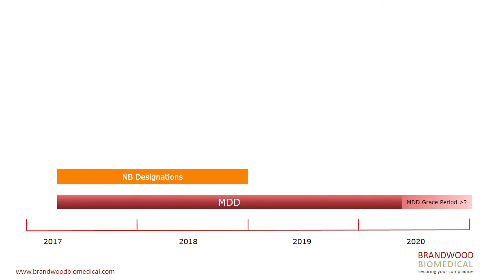Now, notified bodies need to be able to assess manufacturers to the new regulations. But if you're thinking that you're going to steal a march and start now, the problem is that no notified body is yet designated under the new rules. So nobody is yet able to be assessed under the new regulations, even though they've been gazetted and they're now in place. And it's expected that that designation process is going to take some time.